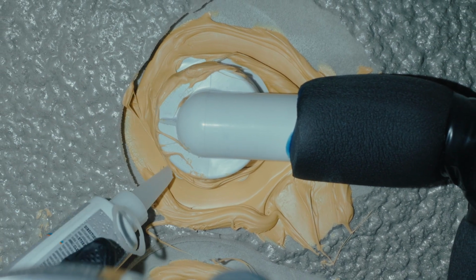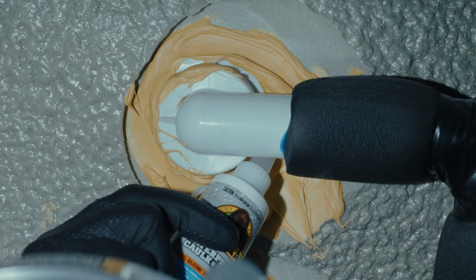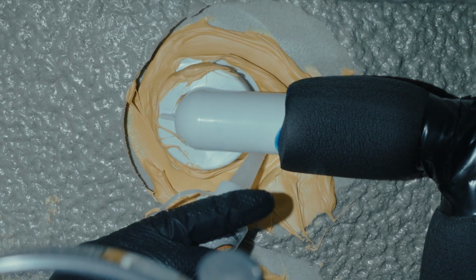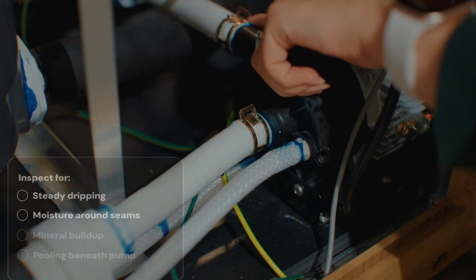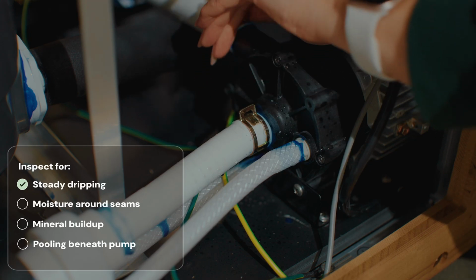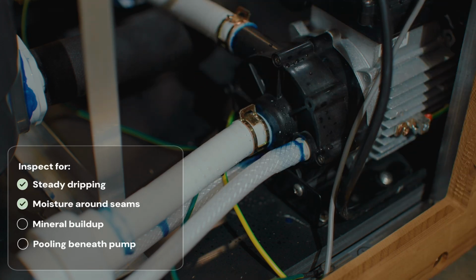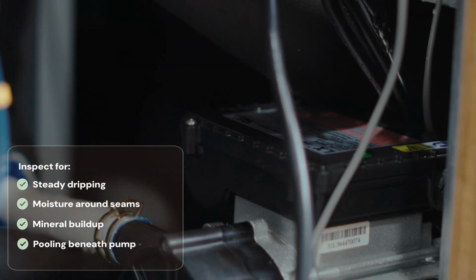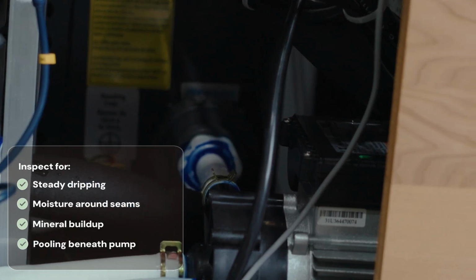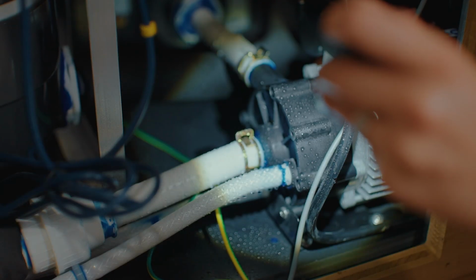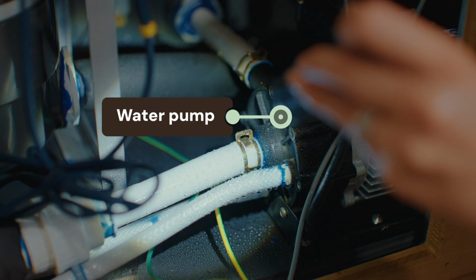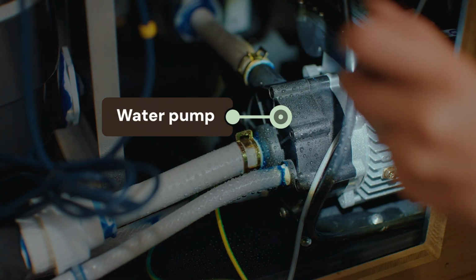While water pump leaks are not especially common, they can occur from failed seals or damaged internal components. Inspect the pump assembly carefully, paying close attention to seams, unions, and areas showing active moisture or mineral buildup. If the source of the leak is confirmed to be within the pump body or internal assembly, the full water pump will typically need to be replaced. For electrical or pump-related repairs, professional assistance from a licensed plumber or qualified service technician may be recommended.